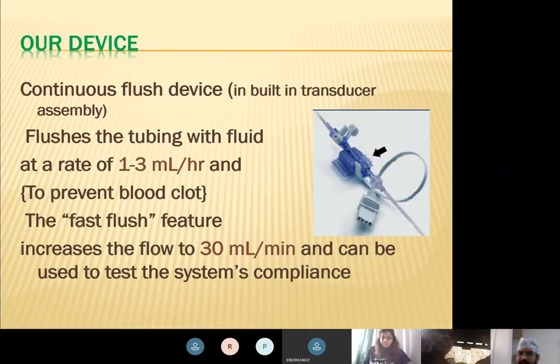So the fast flush feature, which means you're opening up that blue line, pulling up that small blue thing, will cause the flow to increase to around 30 ml per minute. So it is not a good idea to keep on flushing that. If you keep on flushing that, you will give so much fluid that the patient will get fluid overloaded. All right. So why is it there? It is there because we want to understand whether the system is normal or not.